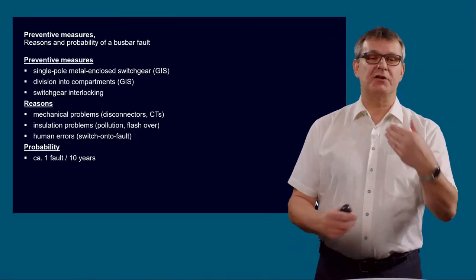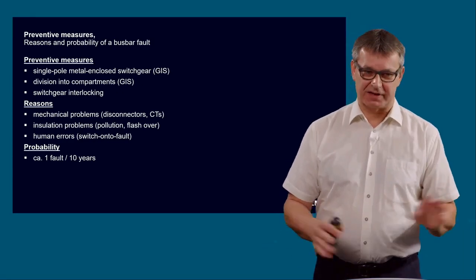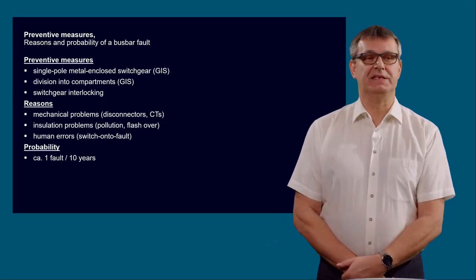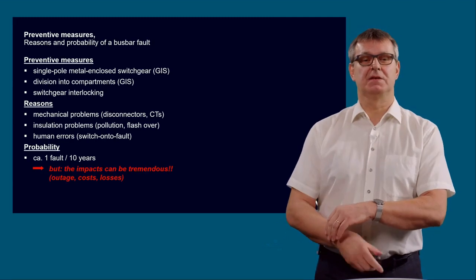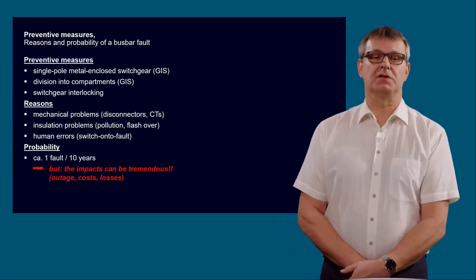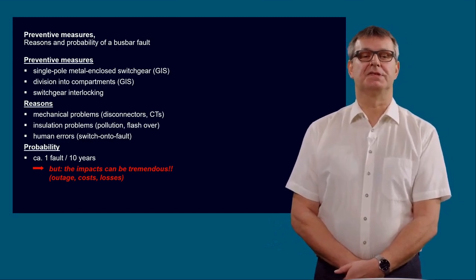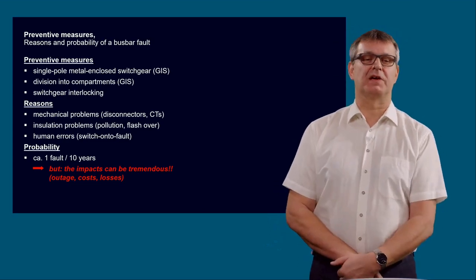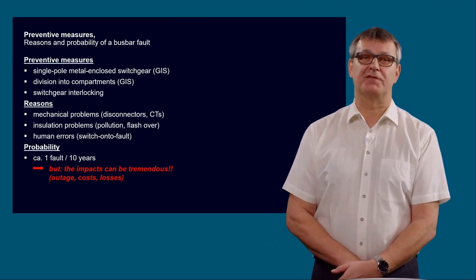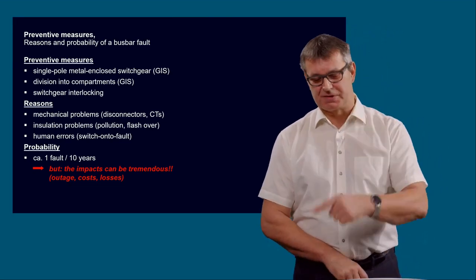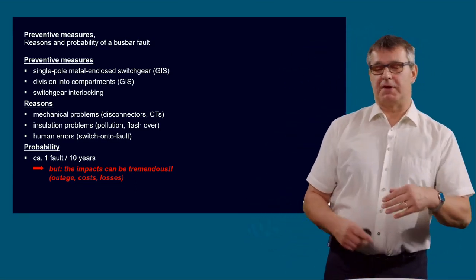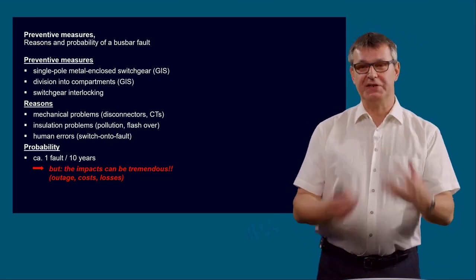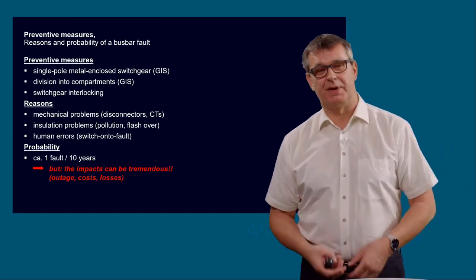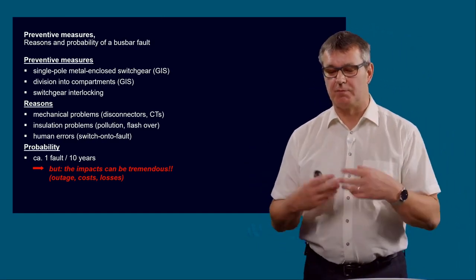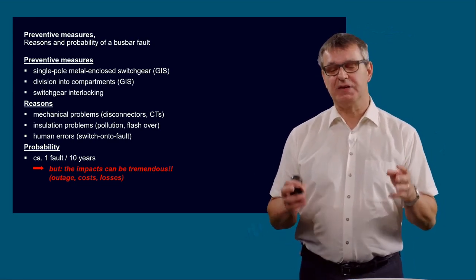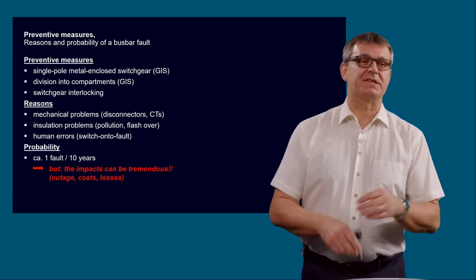Can we switch again? So the average probability, of course only a very rough average, is typically one fault per 10 years to have a busbar fault. But if we have such a busbar fault, the impacts can be really tremendous. We will see it later. And maybe one additional remark: we have only one busbar fault every 10 years. But my former colleague, Matthias Schick, maybe some of you still know him, he said every time that we have the highest probability of a fault per meter. So if you think, okay, the busbars compared to overhead lines of more than 100 kilometers, the probability is higher, but per meter, you have the highest probability in the busbar.